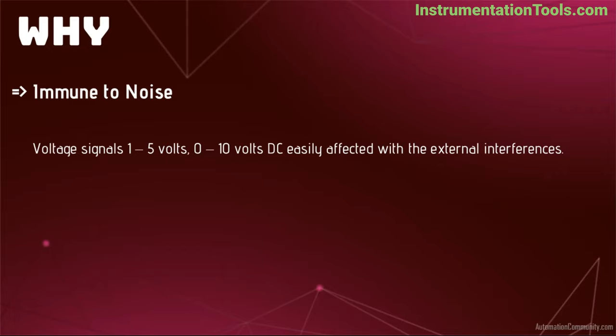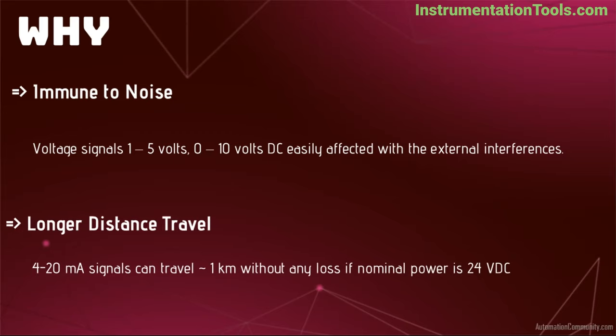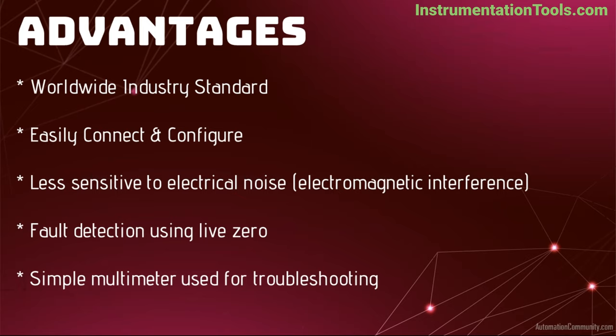Current signals are more immune to electrical noise compared to voltage signals, so the amount of noise or external interference is less. Another advantage is that current signals can travel longer distances — 4 to 20 mA signals can travel approximately 1 km when the nominal power supply is 24 volts DC. The 4 to 20 mA standard makes installation and configuration easy, external disturbances are very less, faults can be easily detected with LIVE ZERO, and a simple multimeter is sufficient for troubleshooting.